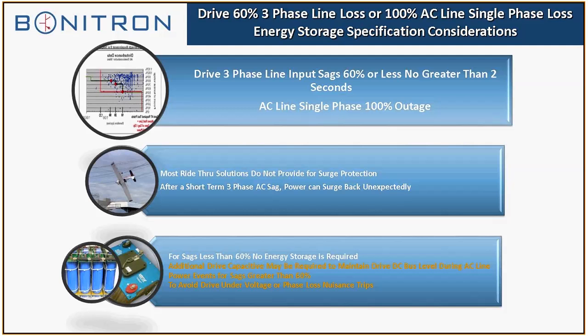For sags less than 60%, no energy storage is required, but in some cases you may have a sag that's a little bit greater than 60%. Between 60, 80, 90%, you have to add some sort of additional drive capacitance to be able to handle that. But that's when you get down to the nitty-gritty of a specification. And usually, when we get requested for a ride-through spec, the customer doesn't know the exact details, so you have to dig in, possibly talk to the utility company to get more information.